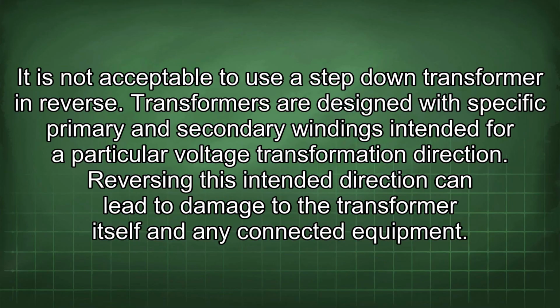It is not acceptable to use a step-down transformer in reverse. Transformers are designed with specific primary and secondary windings intended for a particular voltage transformation direction. Reversing this intended direction can lead to damage to the transformer itself and any connected equipment.